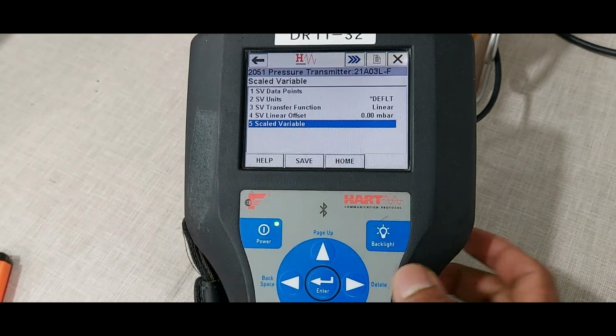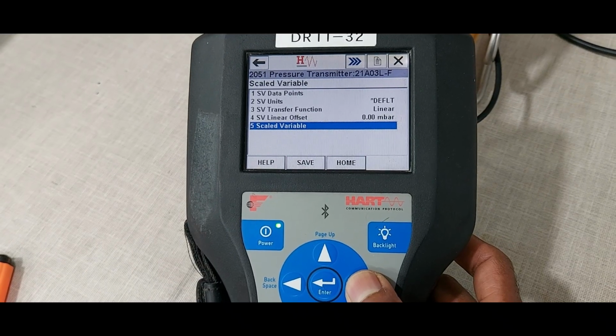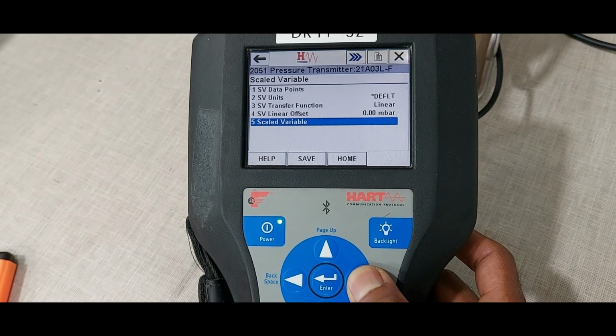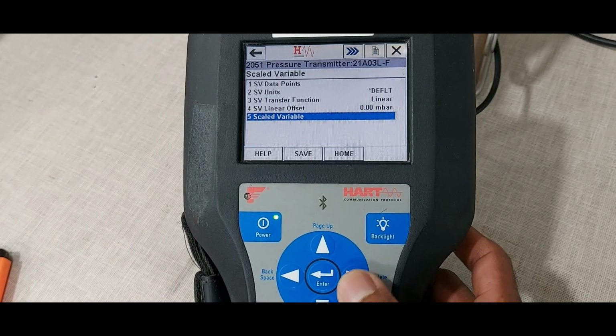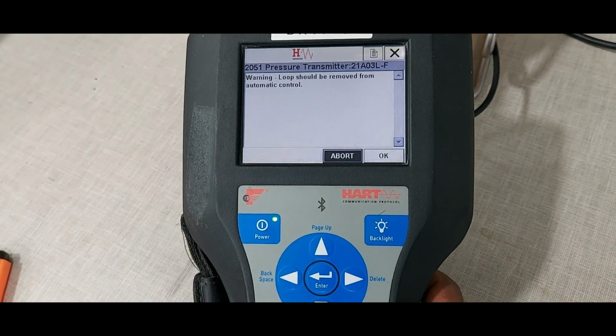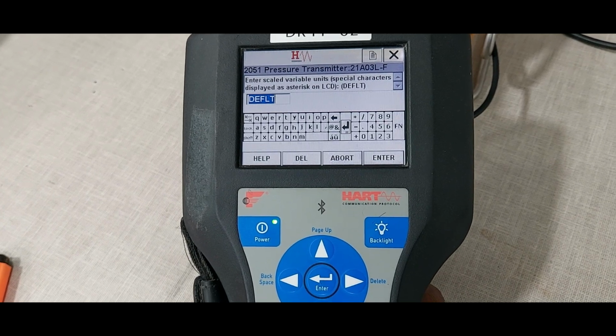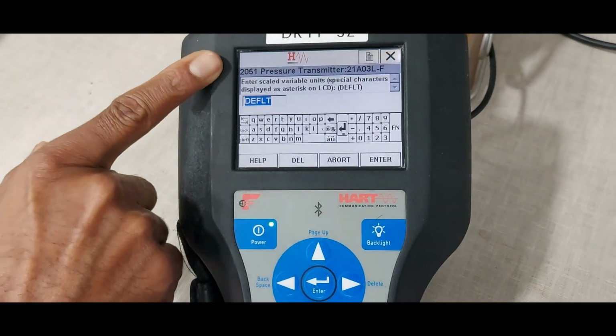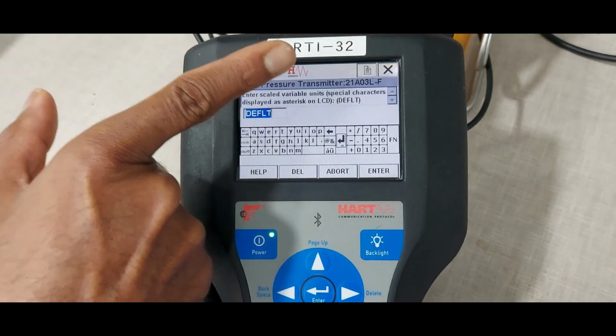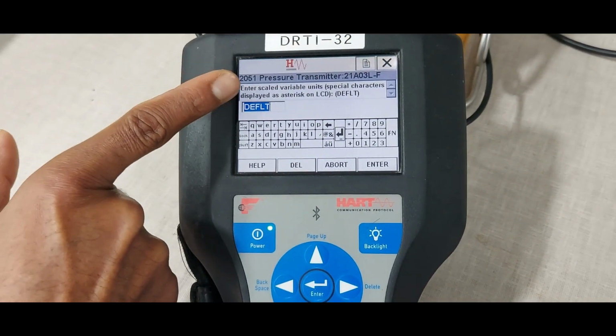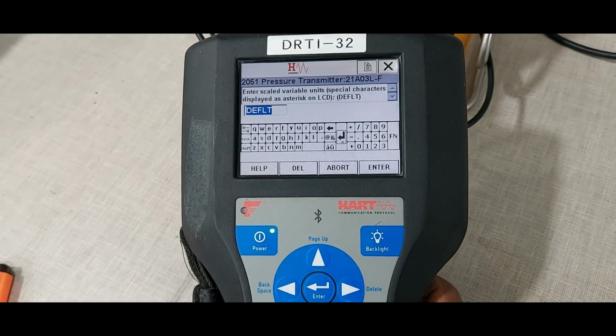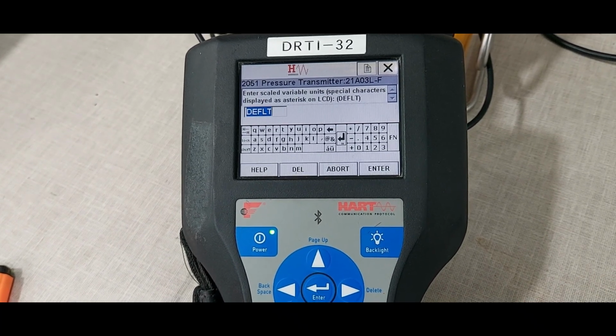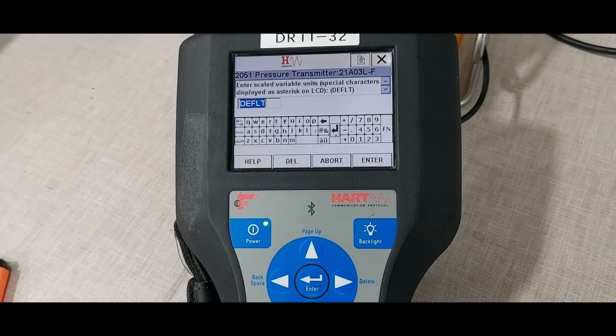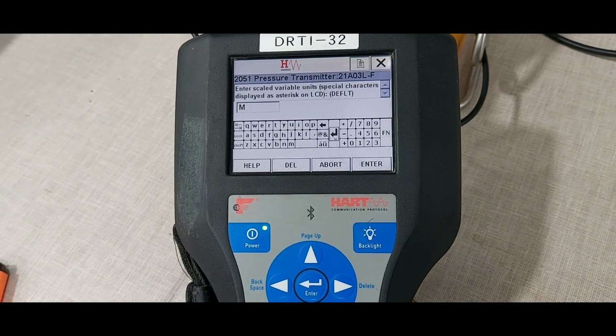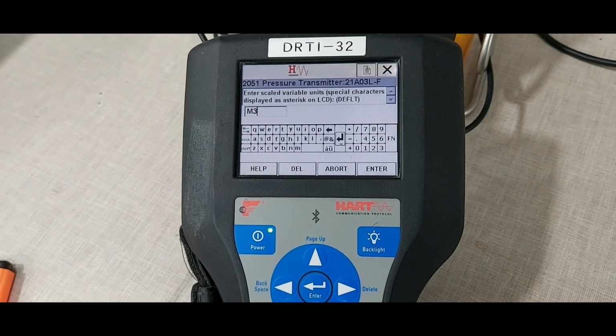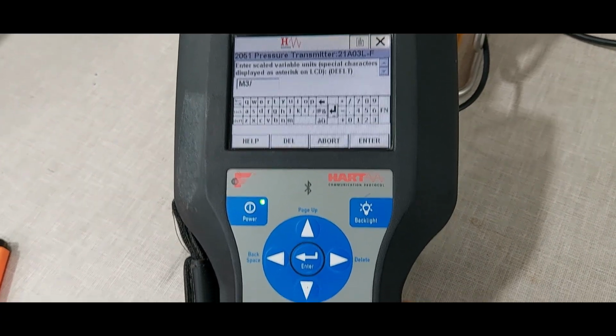Next we are starting the configuration for flow unit, flow range, DP unit and DP range. Selecting number 5. Okay, change the remote controller. Enter the scaled variable unit, special character display. Now we are entering meter cube per hour.